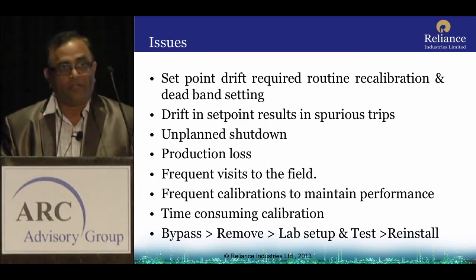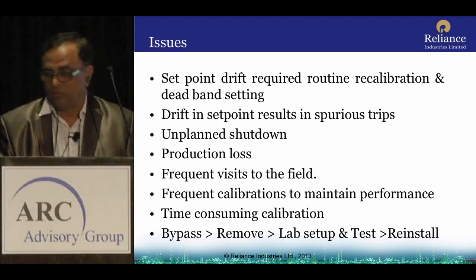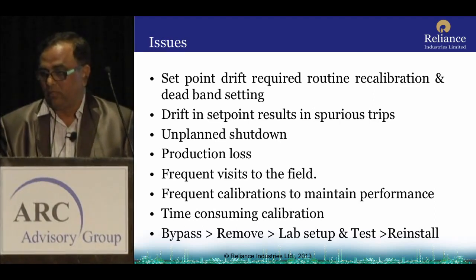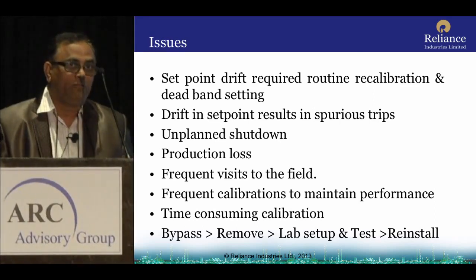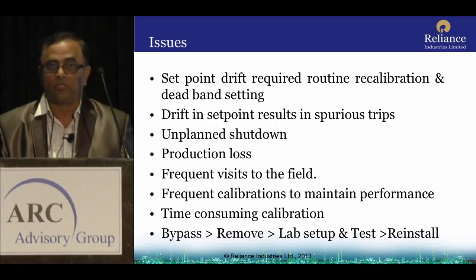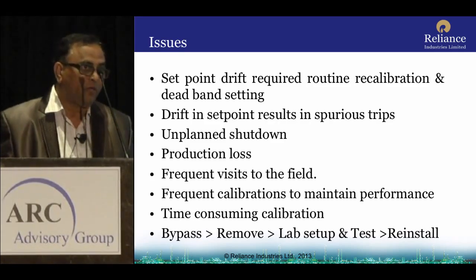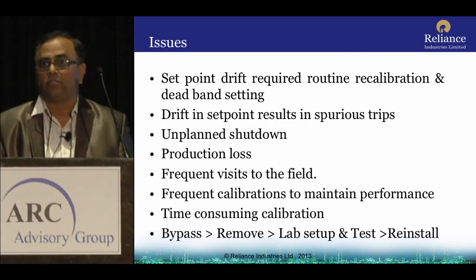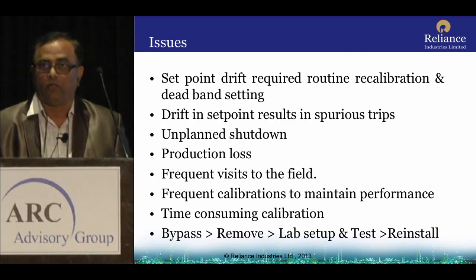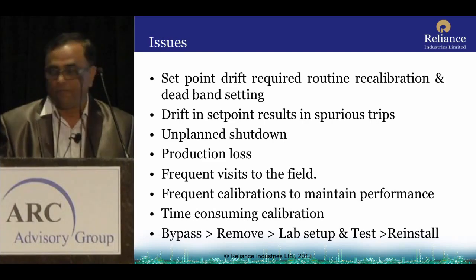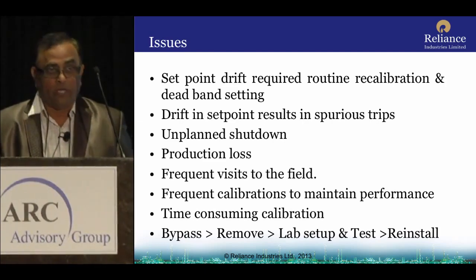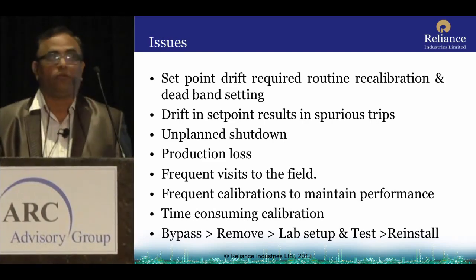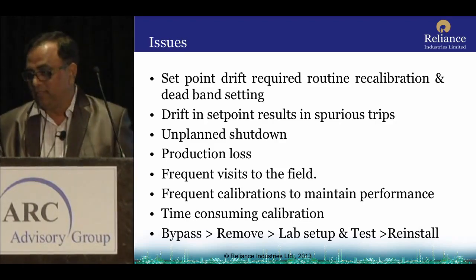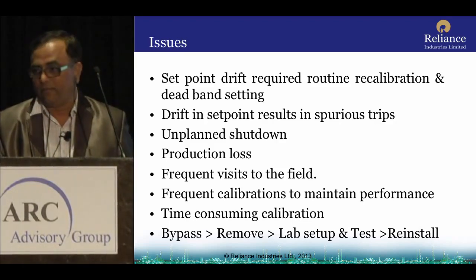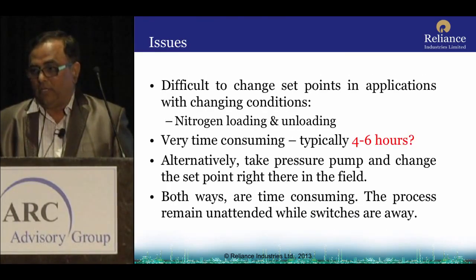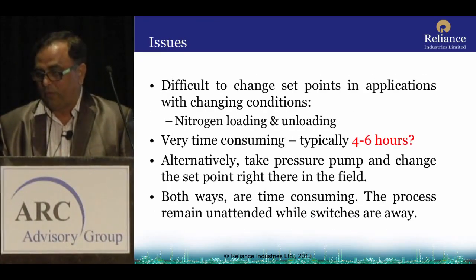Frequent calibration is needed to maintain the performance, to assure the performance of the interlock, and it consumes time, even because we need to bypass a particular parameter, keeping in view what the others are as backup for the parameter we are going to bypass. So, we have to bypass it, remove it, take it to the lab, set it, test it again and reinstall it. That is the problem.